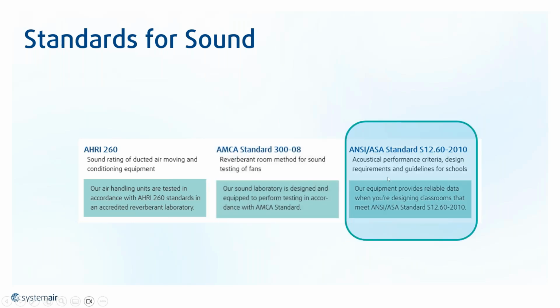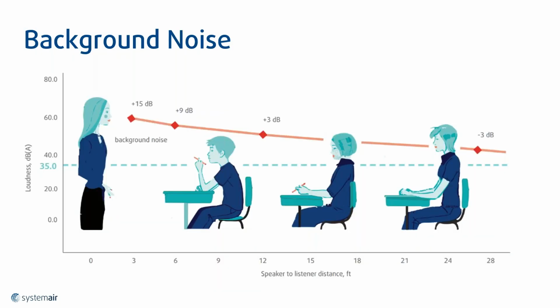On top of that, we finalize it with our equipment tested to ANSI ASA standard S12.60, which is acoustical performance, essentially the guidelines on how to design acoustics for classrooms. It puts a limit of NC 35. The 9 foot by 9 foot by 30 foot classroom standard is there, and all the conditions you need to build the ultimate acoustical classroom. So the background noise is a strict 35 decibels. As you can see, for the student in the back, the sound of the teacher speaking is going to get blurred out, slower and lower, depending on the equipment you have. But if your equipment is designed correctly, then there is no issue. It's a matter of the teacher.